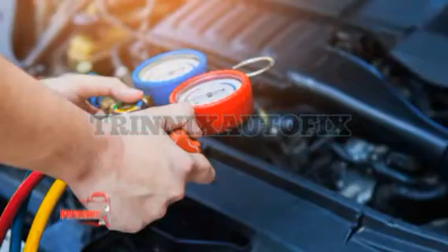If the air conditioning isn't blowing cold air and the low side pressure is too high, it could be caused by issues with the condenser fan. However, there's also the possibility that the system has gotten overcharged with too much refrigerant. 1. Defective condenser fan. When the fan becomes damaged, airflow through the condenser is diminished.